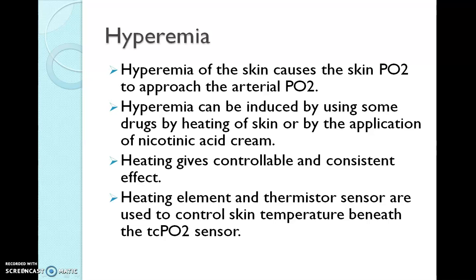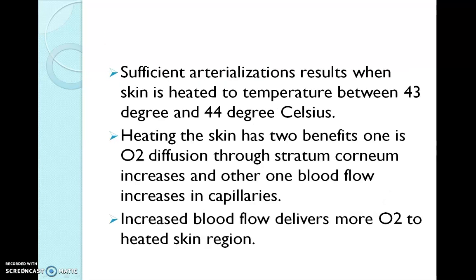Sufficient arterialization results when the skin is heated to temperatures between 43 degrees Celsius and 44 degrees Celsius. This temperature causes minimal skin damage, but with neonates it is still necessary to reposition the sensor frequently to avoid burns to the skin.